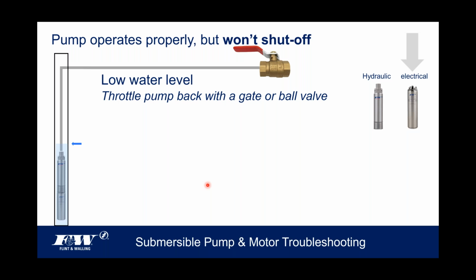So sometimes if it's due to a low water level or a low water table, what some contractors will do is they'll install either a gate valve or a ball valve somewhere on that discharge line, and they'll throttle it back. As they throttle it back, that pump will start to build pressure. Once you get the pump throttled back to where it builds pressure and shuts off, I take the handle off that ball valve, right? I don't want anybody messing with that ball valve from this point forward, so I'd probably take the handle off of it and just leave it like it is. And again, these aren't necessarily long-term solutions, but they can buy some additional time and life out of a submersible pump before it eventually is going to have to be field scrapped.